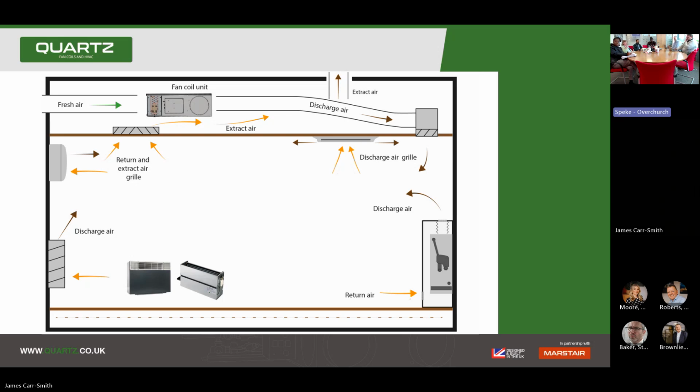On the wall-mounted unit, how close to the ceiling does it have to be mounted? Ideally, you don't want to be too far away. We normally say within 50 mil of the top of the ceiling, so just enough to be able to get the case off to service it. But the higher up you go, the better you get the cling across the ceiling.